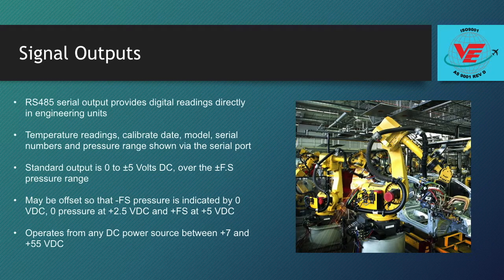The RS485 serial output provides digital readings directly in engineering units. Temperature readings, the calibrate date, model and serial number, as well as the pressure range, are shown via the serial port. The P855 is also available with a standard output of 0 to plus or minus 5 volts DC over the plus and minus full-scale pressure range. This can be offset so that the minus full-scale pressure is indicated by 0 volts DC, 0 pressure at plus 2.5 volts DC, and plus full-scale pressure at plus 5 volts DC.